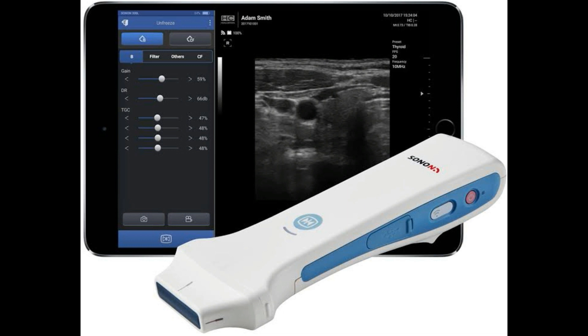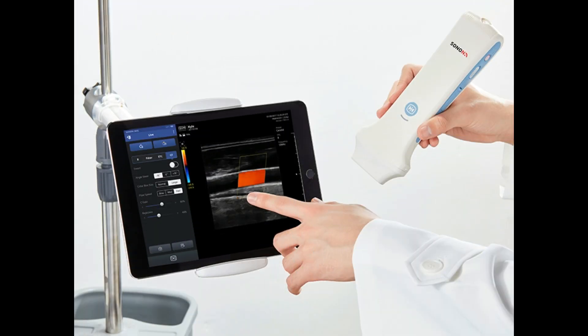Since the introduction of the Sonon 300C convex transducer, the company has been making progress to advance its range of ultrasound devices. Their latest Sonon 300L linear transducer weighs only 13 oz, that is 370 grams including the battery, and features a color Doppler mode for easier musculoskeletal, small parts, and lung imaging. The Sonon series can connect and transmit through Wi-Fi as well as 3G LTE, so doctors always have an internet connection even in remote regions.